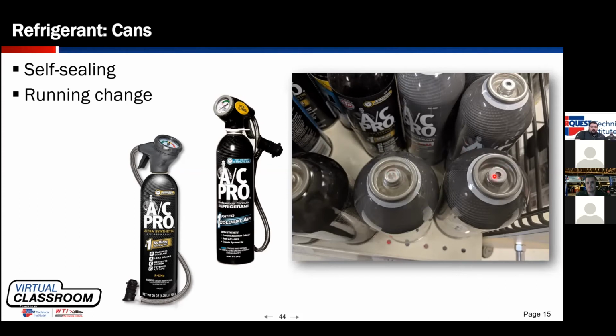So those cans were replaced with these cans that have a resealable valve. There's a ball valve in the top of this can that when I take the tap and screw it on, instead of punching a hole, I'm opening a ball valve. If I try to use a punch top tap for this can on this can, I will most likely damage the valve and may not get any refrigerant out until I take the tap off, in which case the can will no longer be able to seal. So make sure if you are using small cans that you are using the correct tap for the kind of can that you are using.